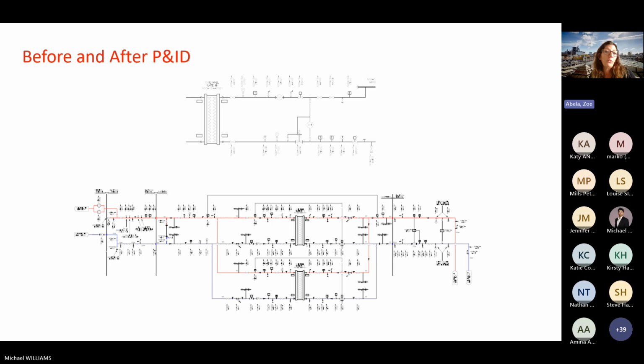The top one is the old plate heat exchanger we had, with very limited controls, all on the primary side. The bottom picture shows the new plate heat exchanger, with more controls on both the primary and secondary side. This allows us to control our return temperatures more efficiently.